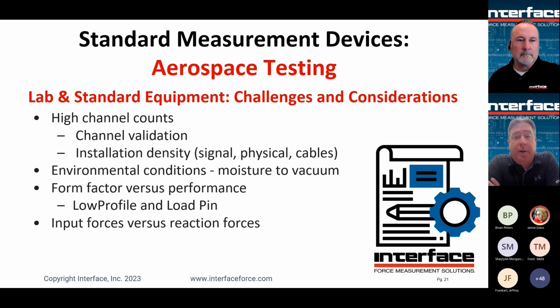So some of the things we've seen done there are different ID strategies for specific channels. TEDS chips are something we've seen used. We're not going to touch on the validity of how it's programmed, but essentially people can use different TEDS ID chips as channel validation tools. So maybe not pulling scaling data off the TEDS chip, but it will allow you to read a serial number and a bridge, perhaps bridge A, bridge B, bridge C. And then essentially that saves you some time in your channel validation, because your data acquisition can just ping the chip and it knows which one it is. That can be pretty handy.